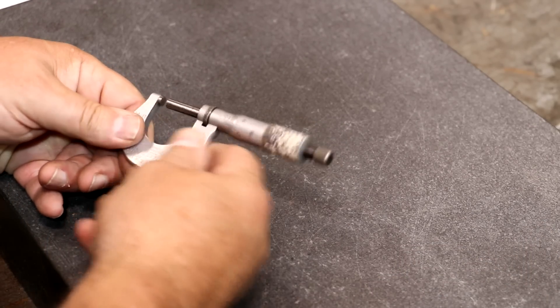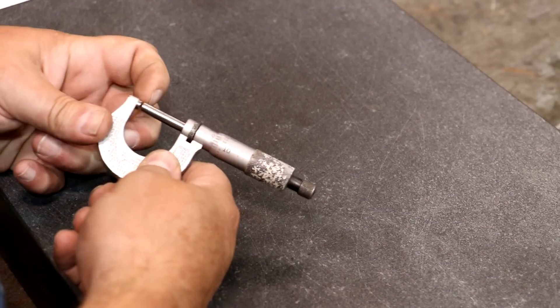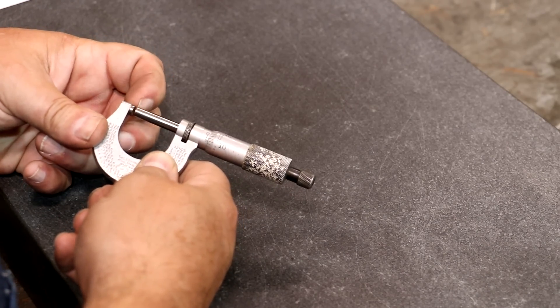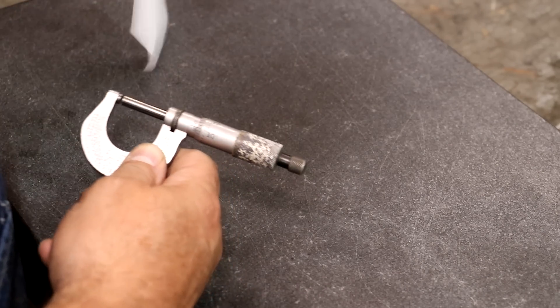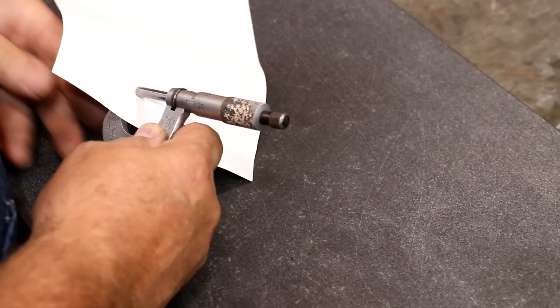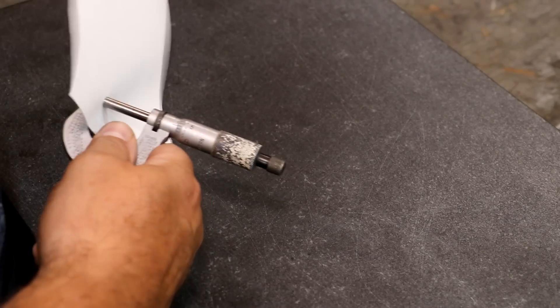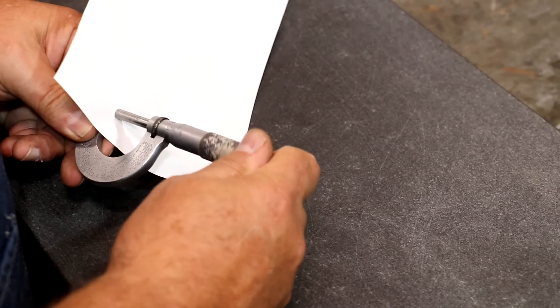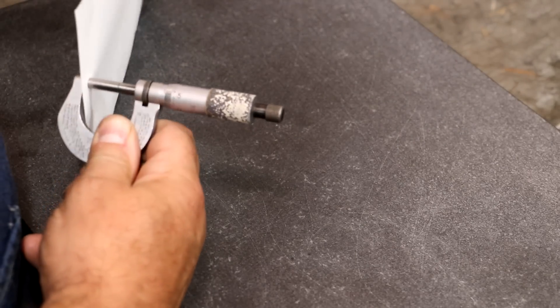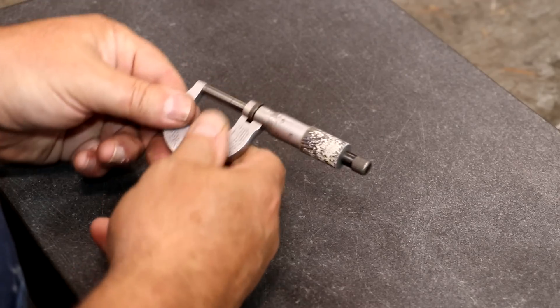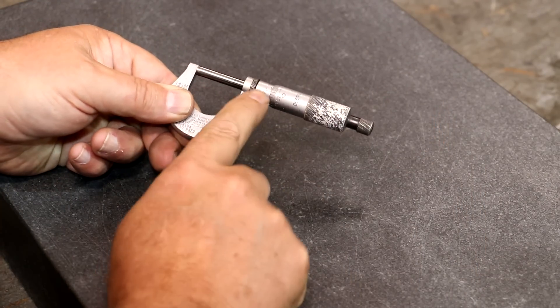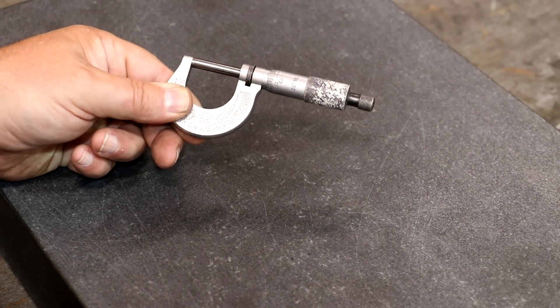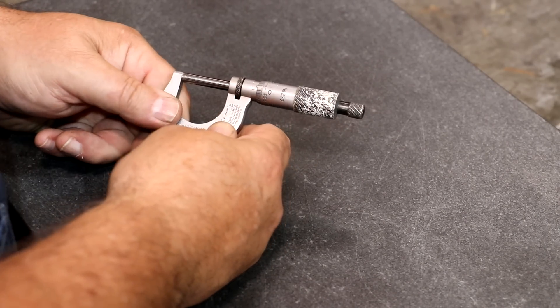Now one thing I will recommend you do is you want to make sure that these faces on the anvils here are clean. One way you can do that, particularly on a small micrometer like this one, is just put a piece of paper in between them and kind of run them down together. And then you can kind of pull that paper out. I got a little bit too tight there and that'll, if there's any kind of trash or just anything on those anvils, it will usually clean it up pretty good. And now what you want to do is just run it down and see where it reads. And you can see this one here is reading right on zero. So this micrometer is in calibration.